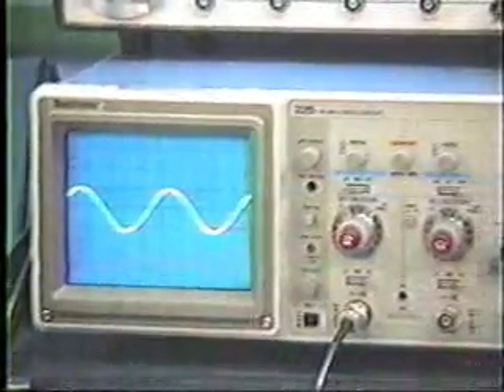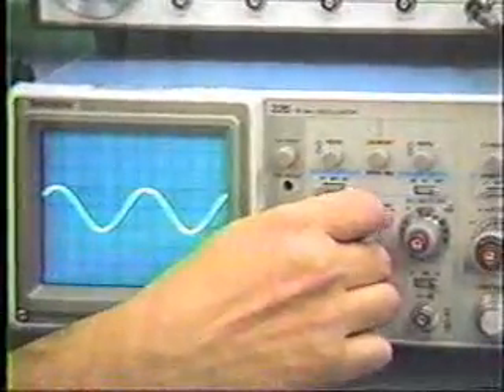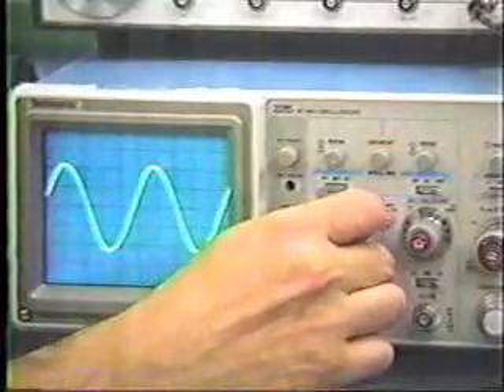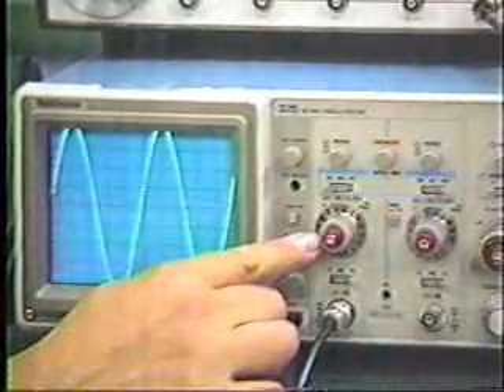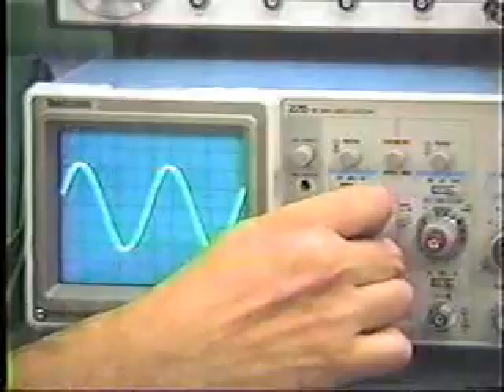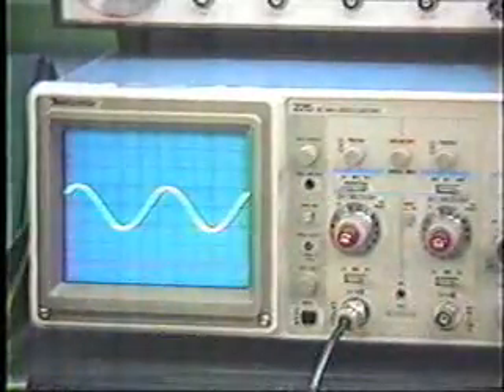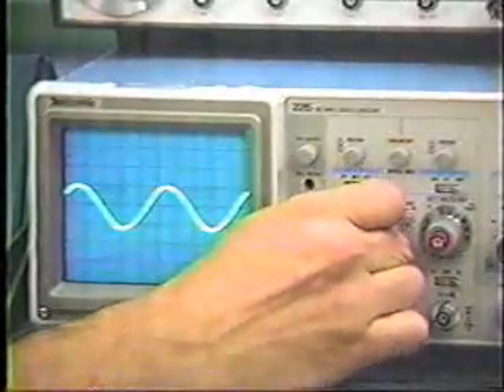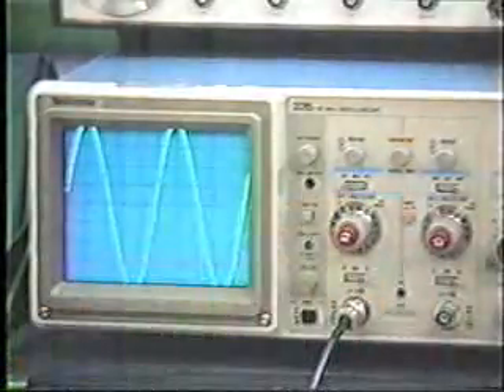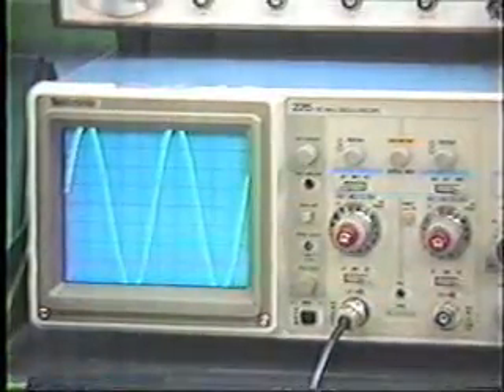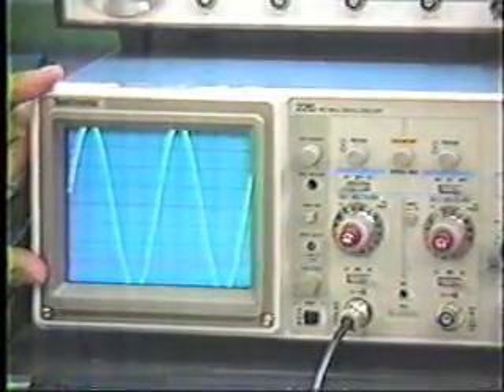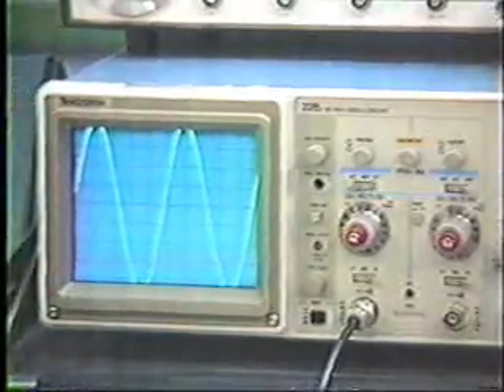If that's not large enough, or if that's too large, then we can simply, by turning this knob here, increase or decrease the gain, and hence the size of the signal that we're displaying on the CRT. Of course, we're not changing the signal. All we're doing is changing the display of the signal, and the calibration factor changes.